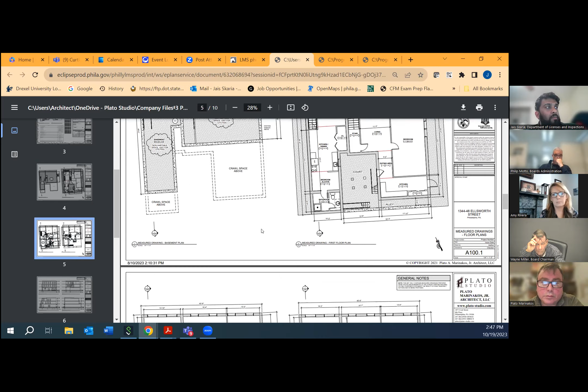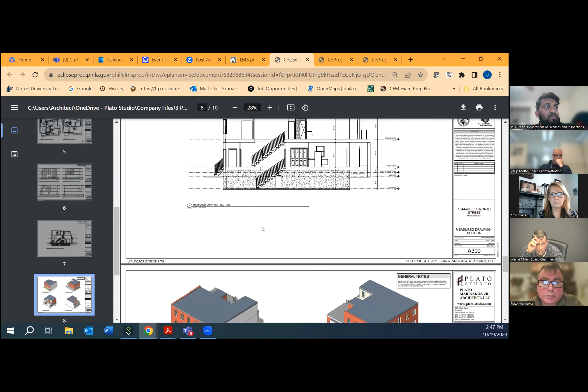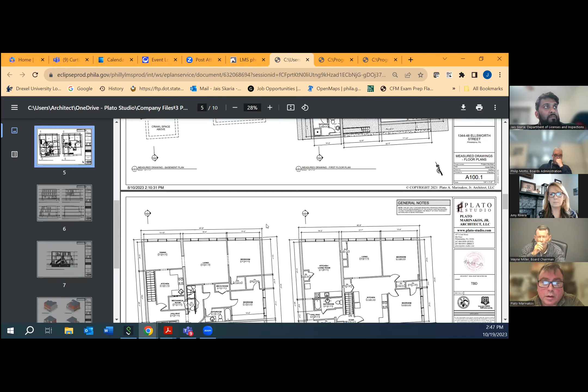I think that's okay. The basement is only accessible from the first floor units. So as long as it's separated and the exit enclosure isn't connecting 4 stories, you're okay. As long as that 1 hour separation holds, the stair enclosure technically only spans 3 stories. But the examiner can't give a thorough review unless you provide all the fire separations between the assemblies.